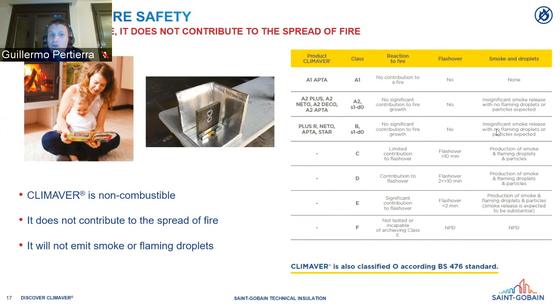So CLIMAVER is non-combustible, and it's very important that it doesn't contribute to the spread of fire and won't emit smoke or flaming droplets. We have tested this not only following the European standard, but also the British standard, BS 476, where CLIMAVER is classified as O. We also have UL 181 certification for CLIMAVER.